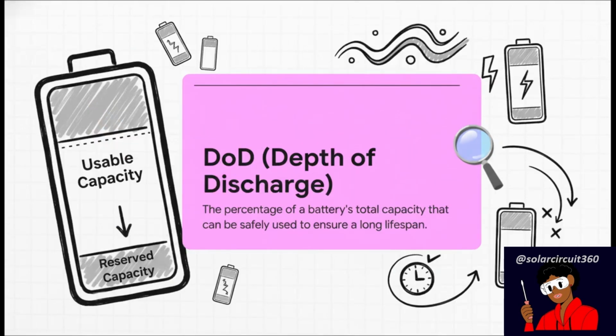Next is something called depth of discharge, or DOD. This one is actually a feature, not a bug. To make sure the battery has a long, happy life, manufacturers build them so you can only safely use a certain percentage of the total juice. For a lot of the LiFePO4 batteries out there, that sweet spot is somewhere around 80, maybe 90%. If you constantly drain it deeper than that, you're just going to wear it out way faster.